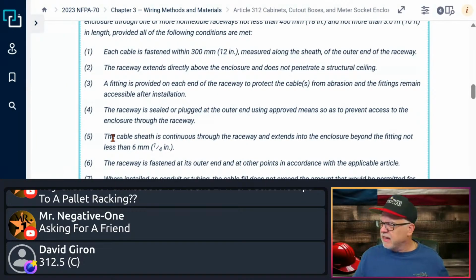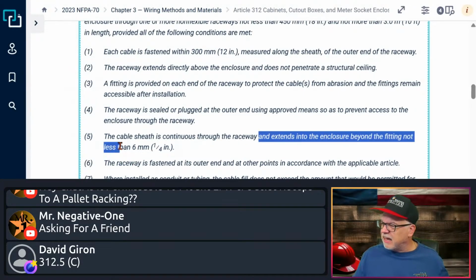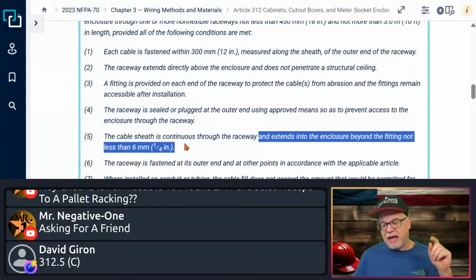I don't have a problem with that. The cable sheathing is continuous. Don't rip it off. Don't take it off. I see that a lot from people as well. Continuous through the raceway and extends into the enclosure beyond the fitting, not less than 1/4 of an inch. We're familiar with that rule.